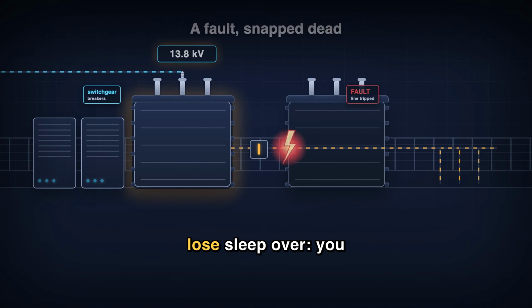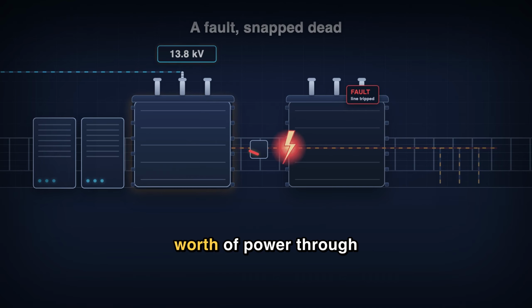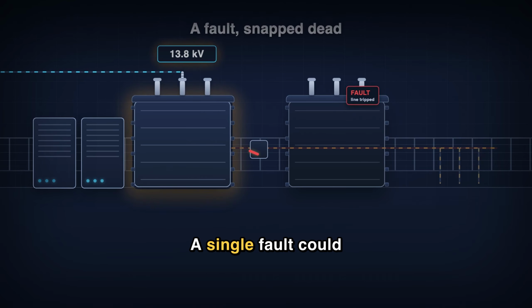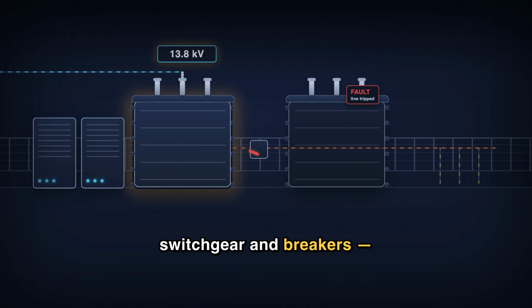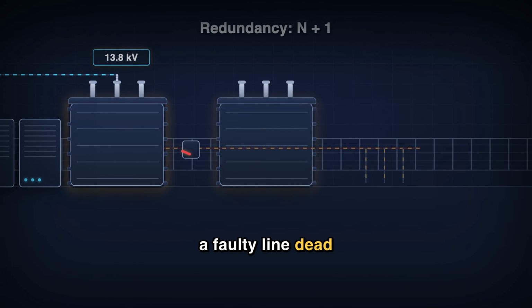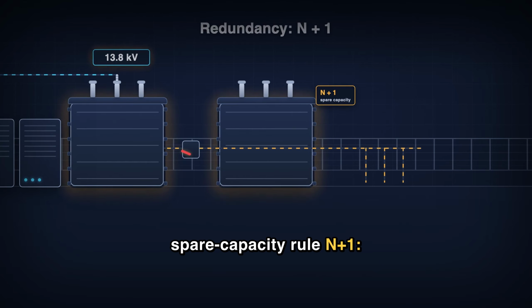Here's the part operators lose sleep over. You can't run a city's worth of power through one box and hope. A single fault could black out the whole site. So substations use switchgear and breakers, heavy switches that snap a faulty line dead in milliseconds, plus redundancy. Engineers call the spare capacity rule N+1. Always one more unit than you strictly need, so one failure never stops the flow.